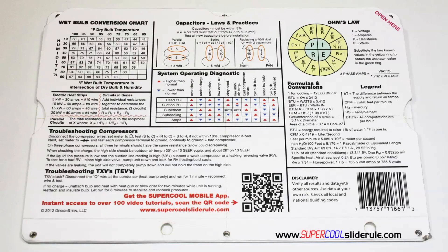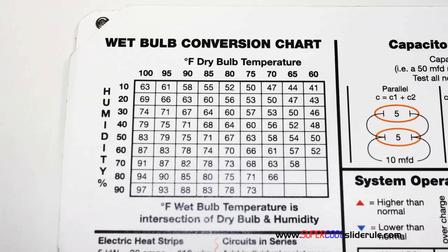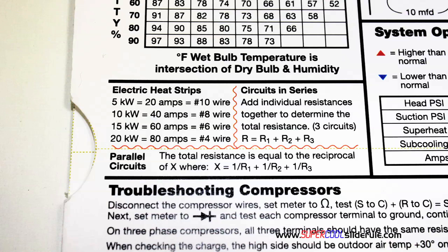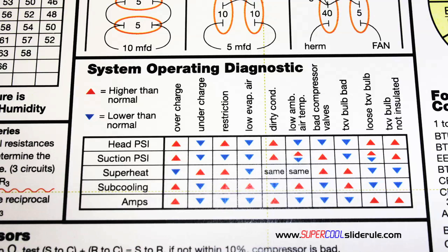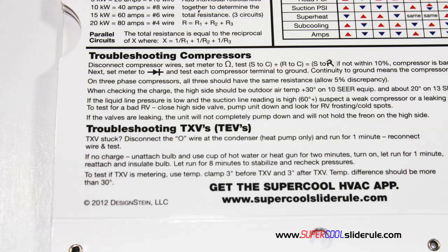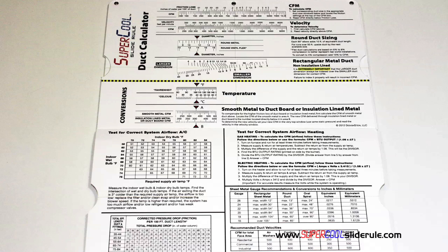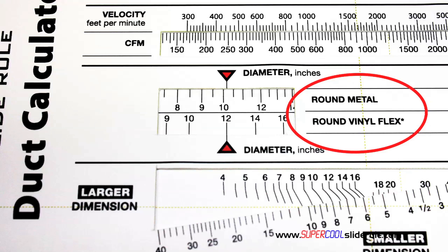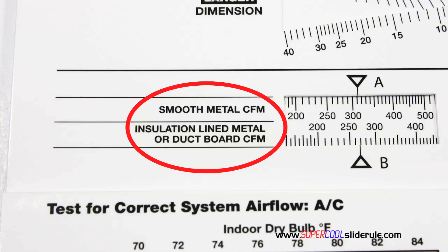The back cover contains required formulas, capacitor rules and practices, a wet bulb conversion chart, how to perform computations on series or parallel circuits, an electric heat strip guide, a complete system troubleshooting diagnostic chart, and how to troubleshoot compressors and TXV. Inside is packed with even more information — it performs sizing of both metal and flexible duct. It has the only direct reading conversion from smooth metal to insulation-lined metal we've ever seen. The majority of technicians have never been taught that if the insulation is on the inside of the ductwork, you cannot size it with a regular duct calculator.